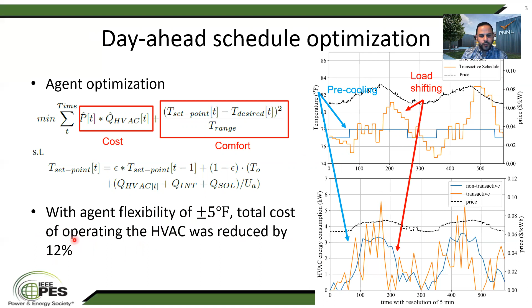We implemented the HVAC agent on this household, for example, on the right, for a couple of days, and we see that two phenomena were developed. We're highlighting here first the pre-cooling, which we notice early in the morning when the prices are relatively low. So the HVAC agent reduces the temperature, which pushes the HVAC to consume more and make use of the lower prices. And later in the day when the prices are high, the temperature set point goes up, which reduces the consumption of the HVAC. And this is basically the trade-off. It will try to consume at the right times of the day, which maintains the comfort and at the same time saves on the energy cost. For the plus or minus 5 degrees Fahrenheit flexibility that we consider in this example, we got a 12% reduction on the total bill for this house.